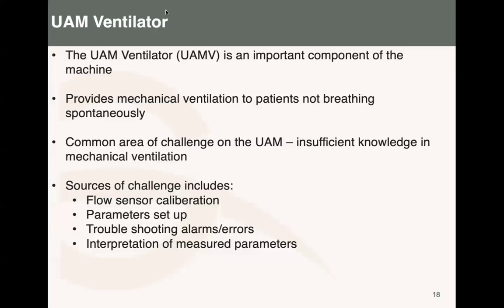Another challenge we've encountered is parameter setting, and it's even worse when it comes to pressure. The machine has volume, pressure control, and continuous modes. They're all challenging to use, but the main challenge is when someone wants to use pressure control. We've also seen challenges with alarms, setting the limits, and setting exactly what you want. Interpretation is also difficult, because remember there are parameters you set, but also measured values, and most of us have some difficulty interpreting what the machine is telling us.